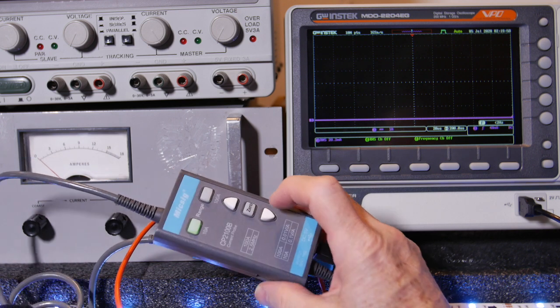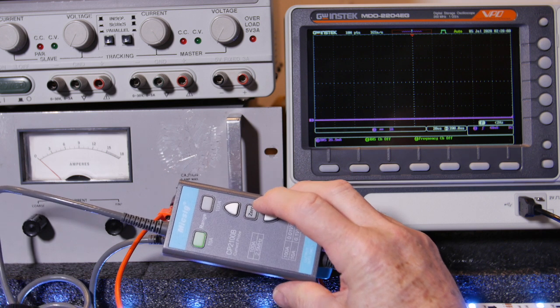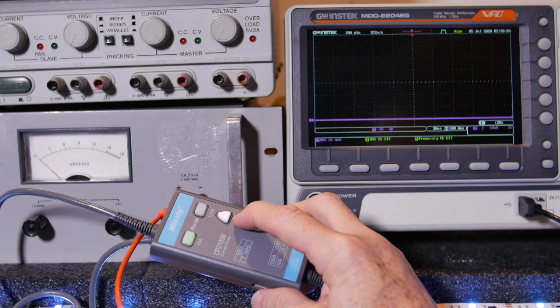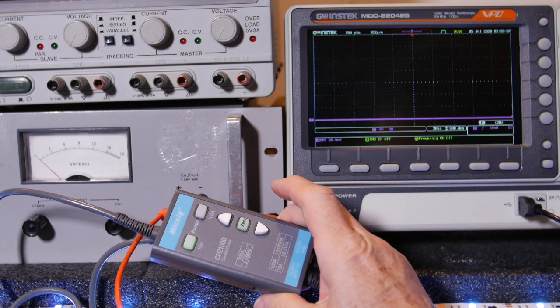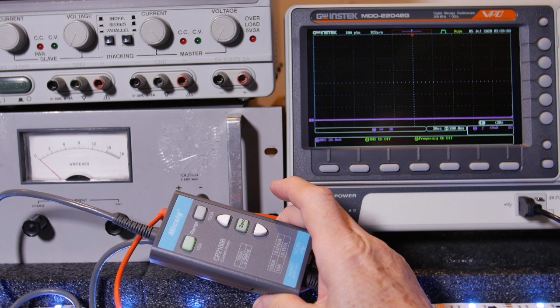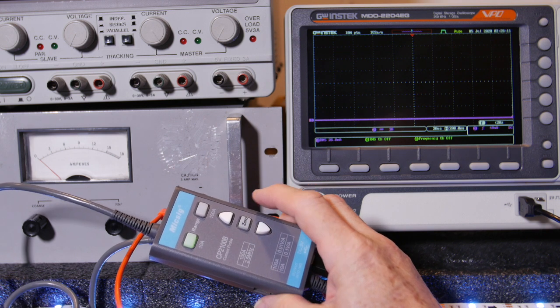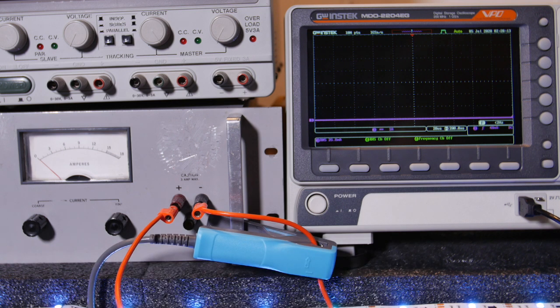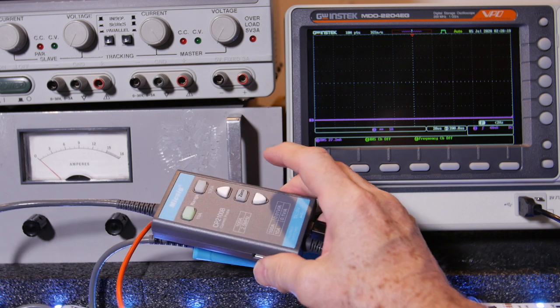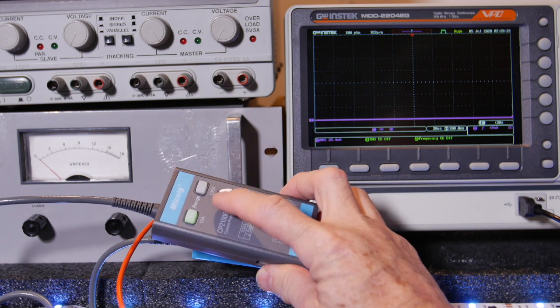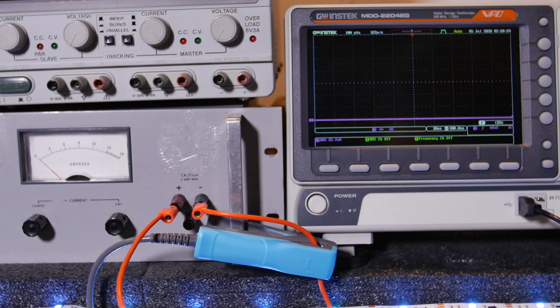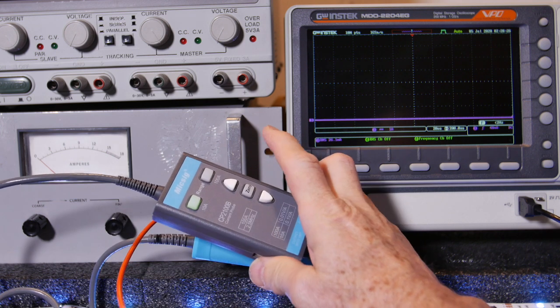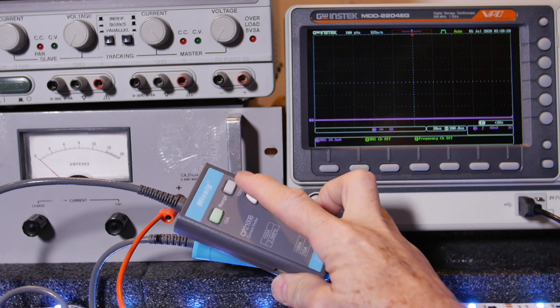By the way, let me show you something. When you zero this out, watch the light go on here at 0. And then you hear the beep, and then it goes off. If it beeped like 3 times, like beep, beep, beep, it means it wasn't a good 0. What we want to do is go above 10 amps and show you what this guy does. And then we also want to go to the 100 amp setting and see how accurate it is.